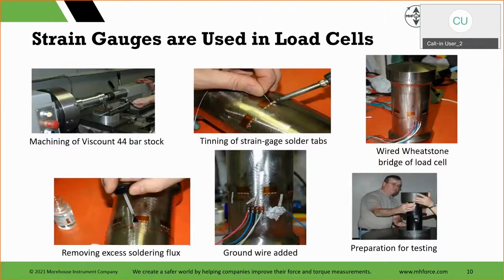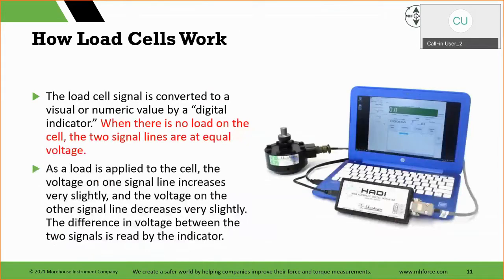Here's our old million-pound standard. What we did, just part of manufacturing load cells, we used a specialty material, Viscount 44 bar stock. Then we tinned the strain gauge solder tabs, wired the Wheatstone bridge of the load cell, lots of wiring there. Removed excess solder flux, and a ground wire was added. If you ever see load cells that kite or are very unstable, it might be because they're not grounded properly, and the load cell tester can test that. And then at the end, preparation for testing.